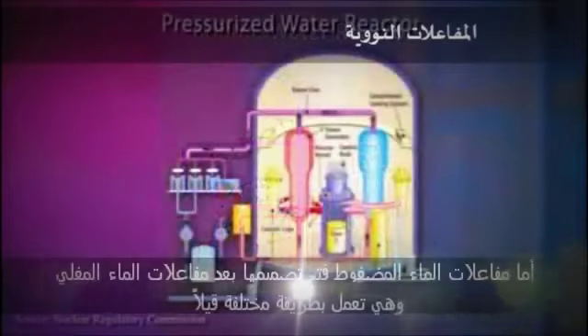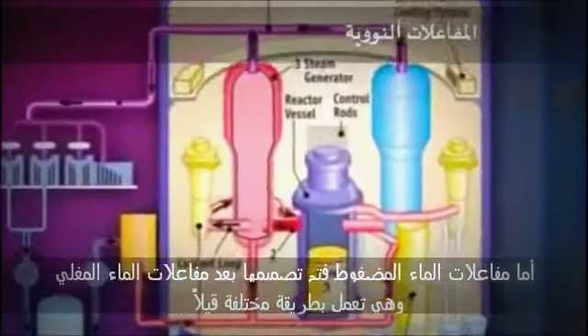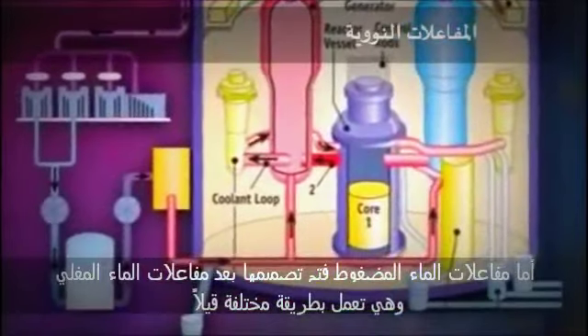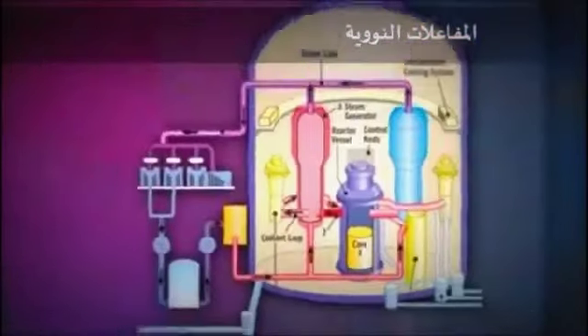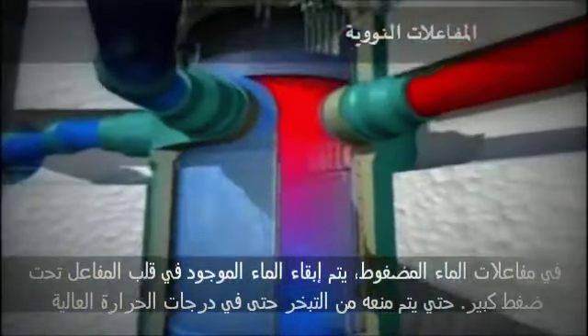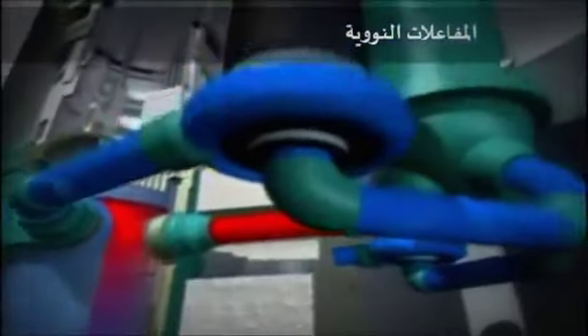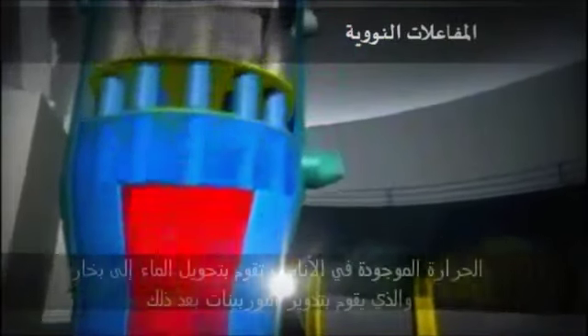Pressurized water reactors, or PWRs, were developed after boiling water reactors and work in a slightly different manner. In a PWR, the water in the reactor tank is under pressure to keep it from boiling, even though it reaches very high temperatures. In the steam generator of a PWR, water passes through thousands of small pipes. The heat in the pipes turns the water to steam, which then drives the turbine. The turbine powers the generator, which in turn produces electricity.